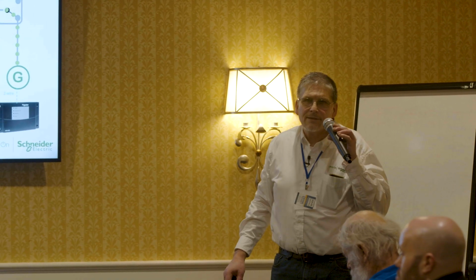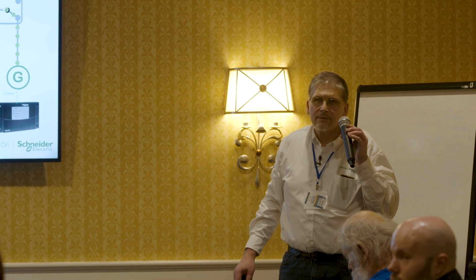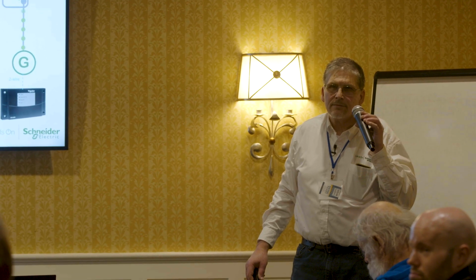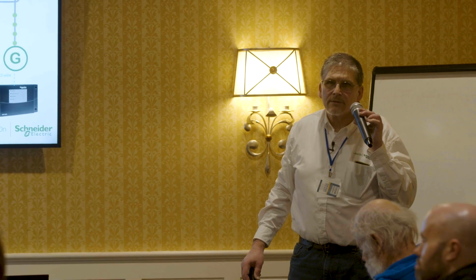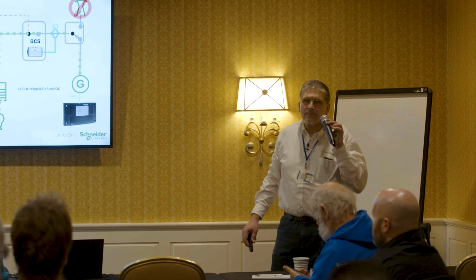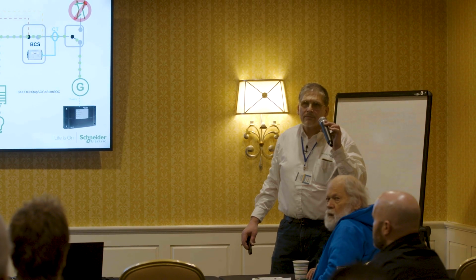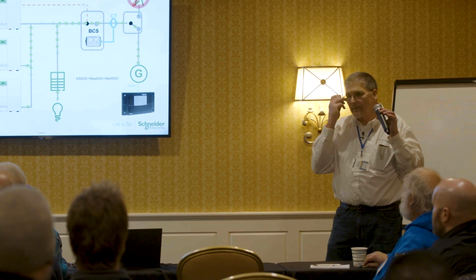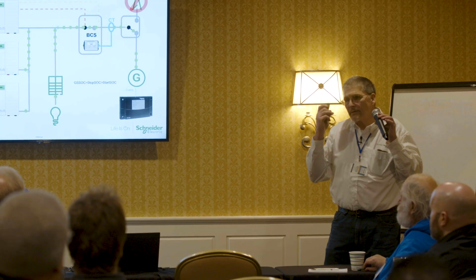Yeah, you have to be careful with that. Why would you manually start the customer's generator? Well, stuff happens. This actually goes with my question. A lot of these generators have general maintenance where they turn on at a certain period, at a certain time, and most customers want it at like 2 o'clock in the afternoon. And on a bright sunny day, your batteries are charged and you have power coming in from your PV. Your generator's going to start automatically unless you program it otherwise.